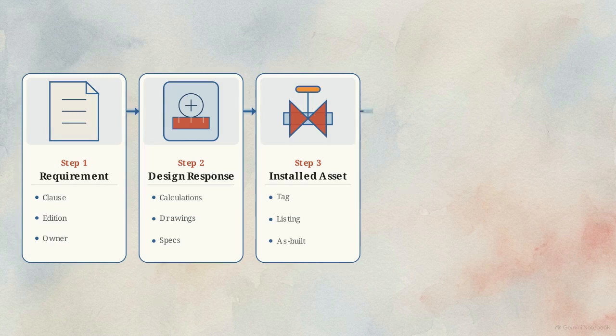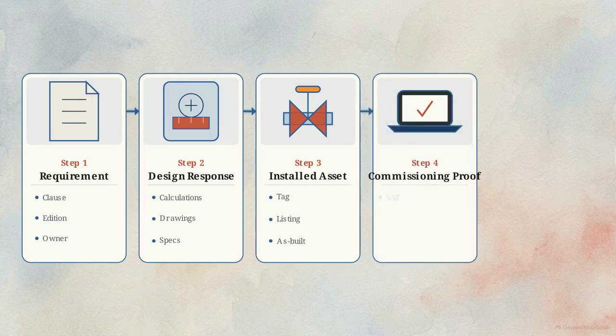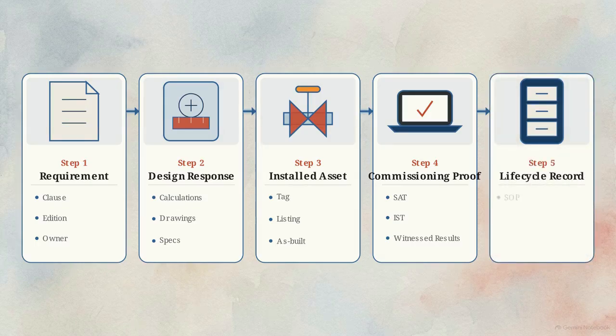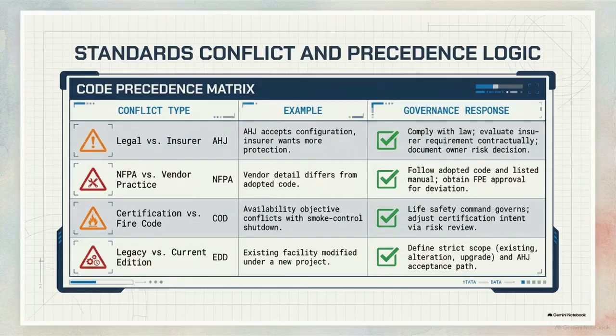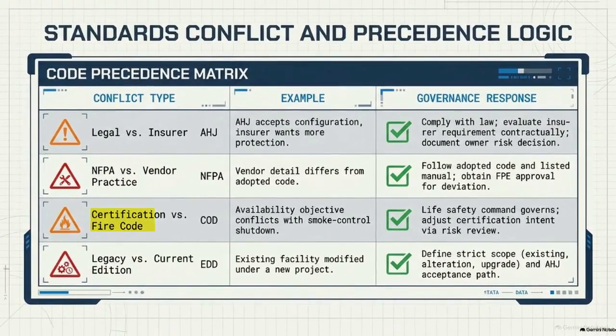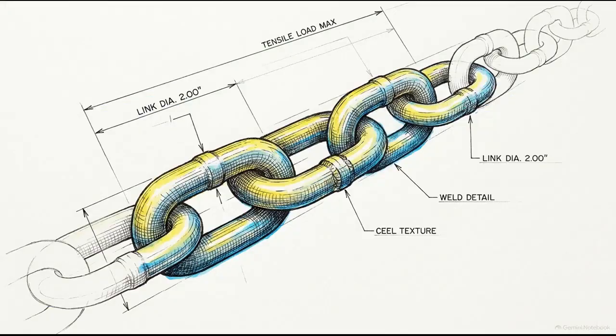But installation is only a midpoint. It requires commissioning proof, witnessed results from site acceptance testing or integrated system testing. Finally, the system must be maintained. Step 5 ties the physical hardware to ongoing lifecycle records, standard operating procedures, and impairment logs. This matrix maps how we resolve the conflicts that inevitably arise between these different evidence sources. In the certification versus fire code row, if an IT availability objective conflicts with a smoke control shutdown requirement, life safety command strictly governs. True compliance is an unbroken chain. If any code requirement cannot be directly mapped, all the way to a field test record and an ongoing maintenance log, that facility is exposed.